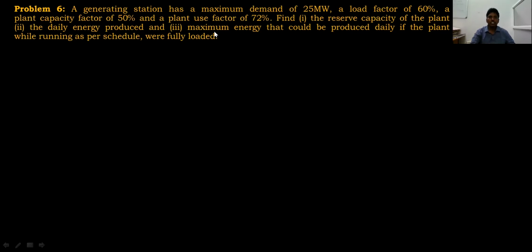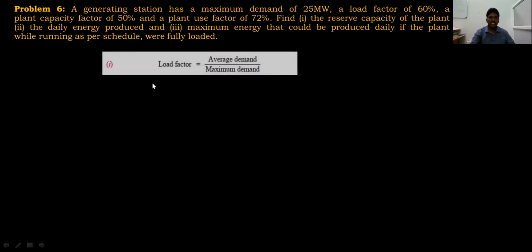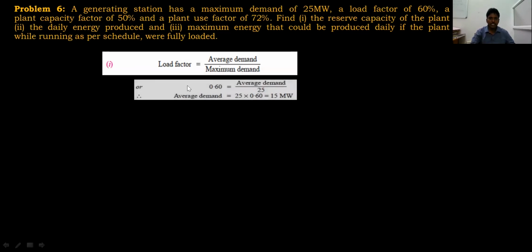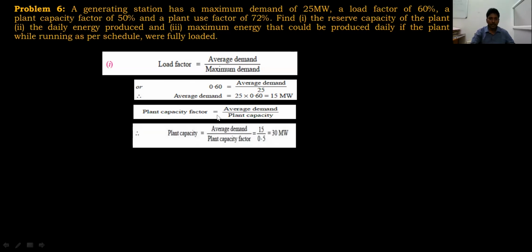And the third question is the maximum energy that could be produced daily if the plant is running as per schedule or fully loaded. First thing is load factor is equal to the average demand by maximum demand. Load factor is already given as 0.6, that is equal to average demand divided by 25. That gives you average demand is equal to 25 into 0.6, that is 15 megawatts. And plant capacity factor is equal to average demand divided by plant capacity. Plant capacity is equal to average demand by plant capacity factor. That gives you 30 megawatts.